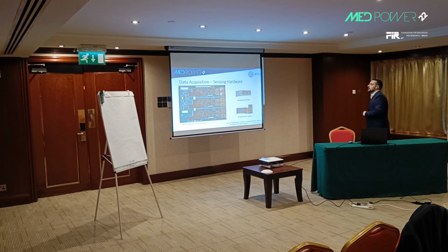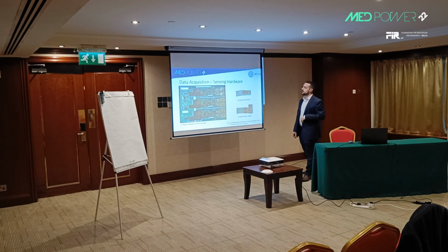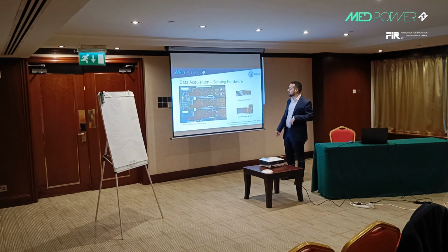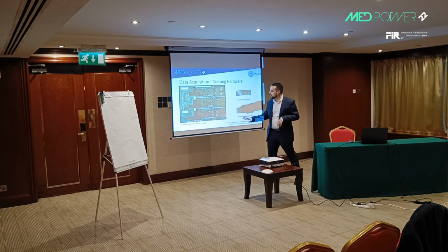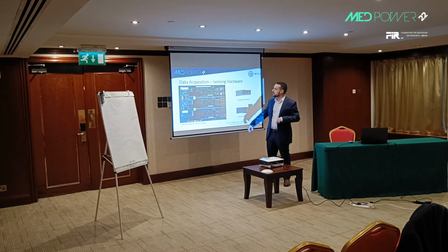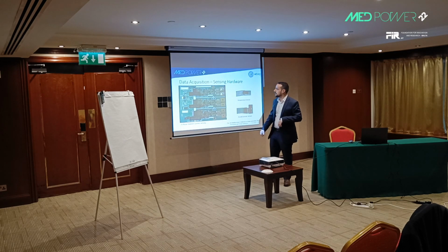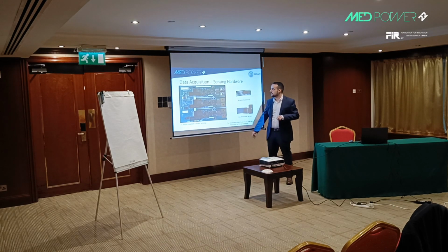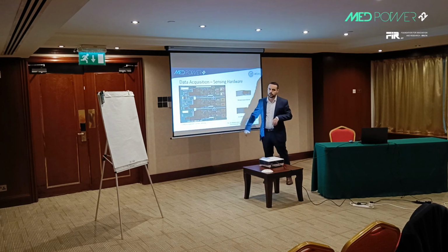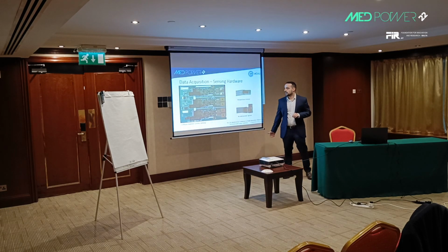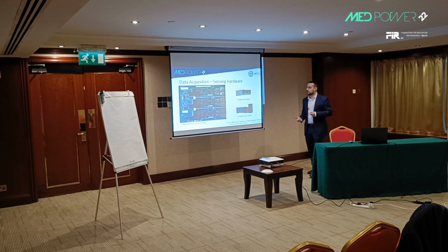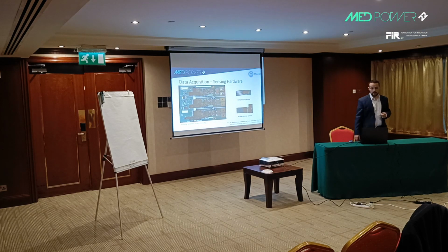So this is the hardware developed. We have here temperature sensor ICs, an accelerometer to monitor vibration, and here we developed a three-phase, fully isolated, for each phase obviously, current sensing circuit. It was possible to use this measuring technique, the shunt-based measuring technique, because it was a low power motor, so the current we draw from it is small. Otherwise, power loss from the resistors would be quite strong.